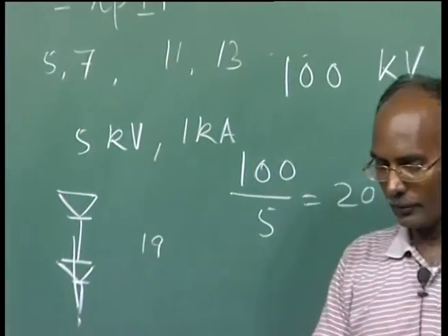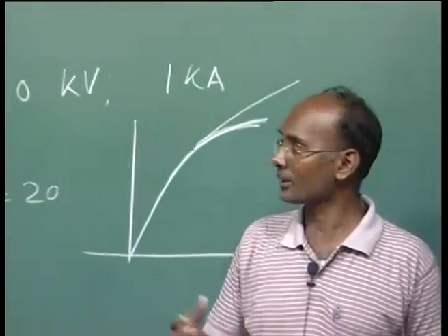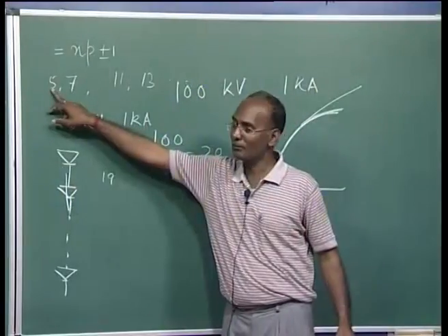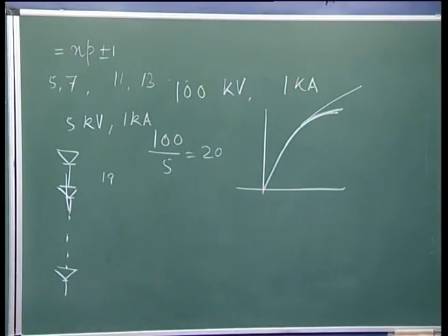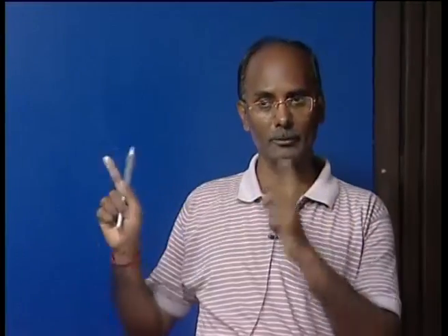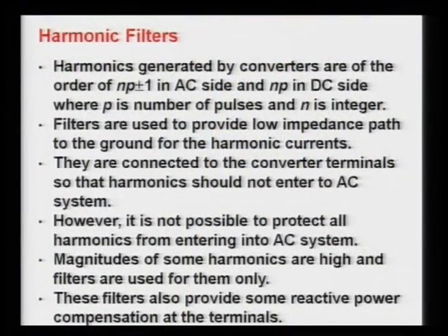As you know, as the frequencies increase and we put filters for them, the size of the filter here will be smaller compared to the 13th, again due to the L and C combination for tuning those components. So as I said, these filters also provide reactive power support at the fundamental frequency that is required for the smooth operation of the HVDC link.